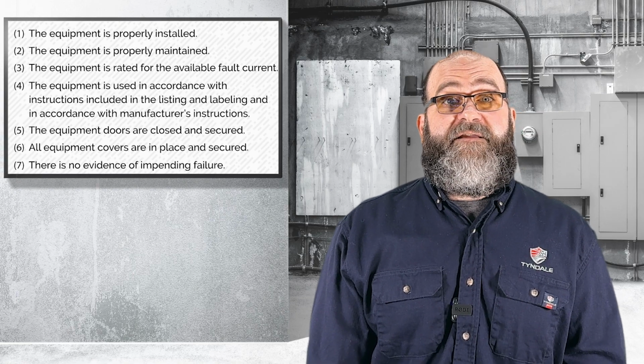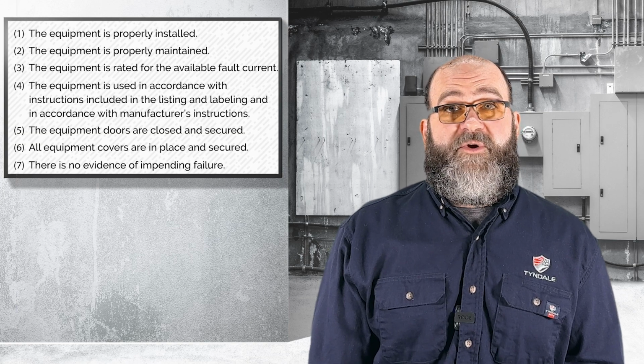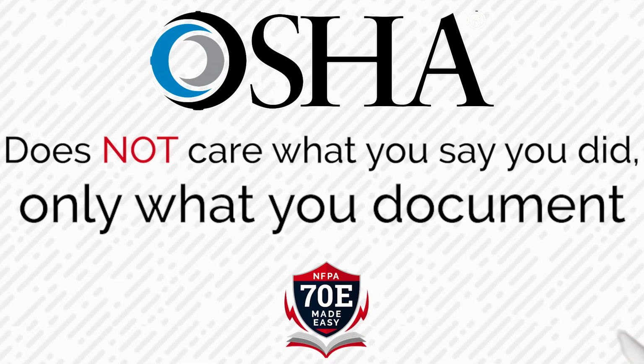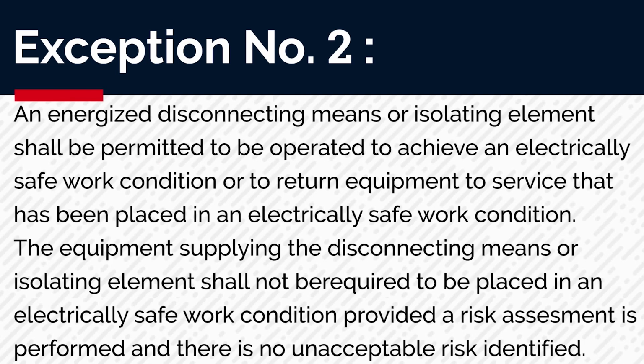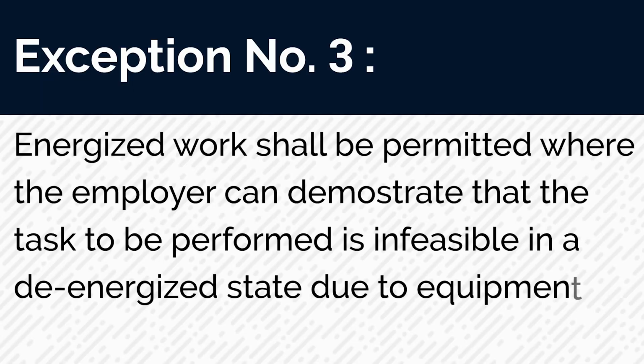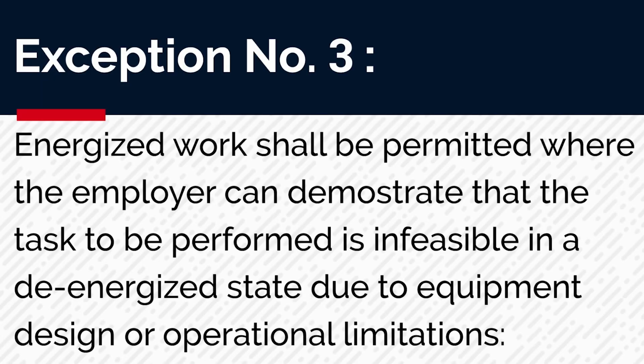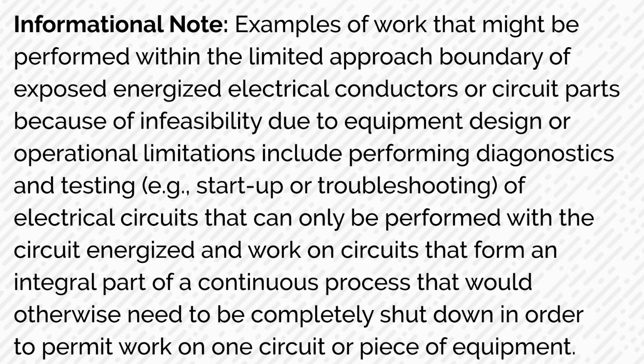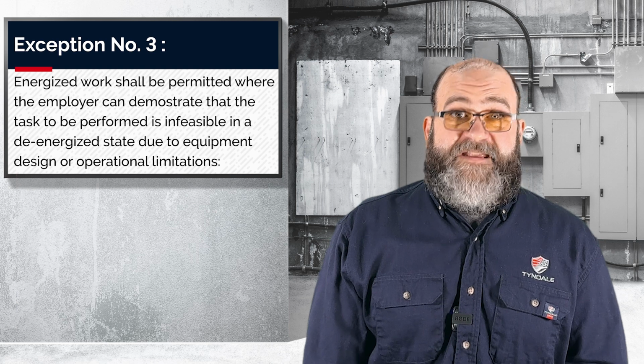Also, before you say equipment is maintained, remember that most organizations, including OSHA, don't care about what you say. They only care about what you document. You have to document this electrical maintenance program. I'm going to leave exception number two alone as it's pretty self-explanatory, but exception number three tells us that energized work shall be permitted where the employer can demonstrate that the task to be performed is infeasible in a de-energized state due to electrical equipment design or operational limitations. This would include, but is not limited to, tasks such as testing, troubleshooting, startup, etc.